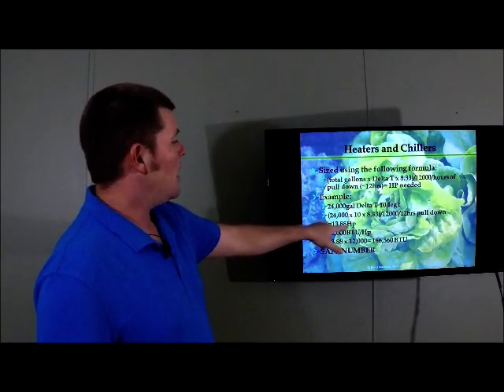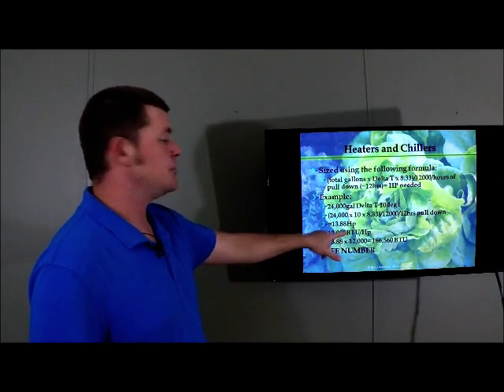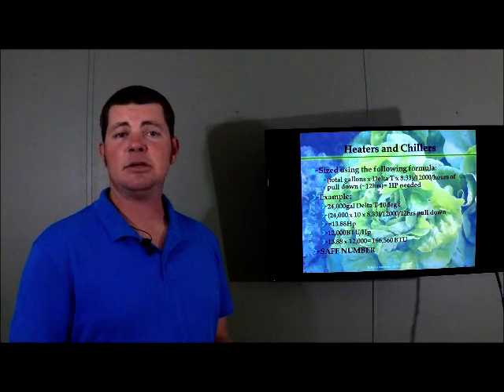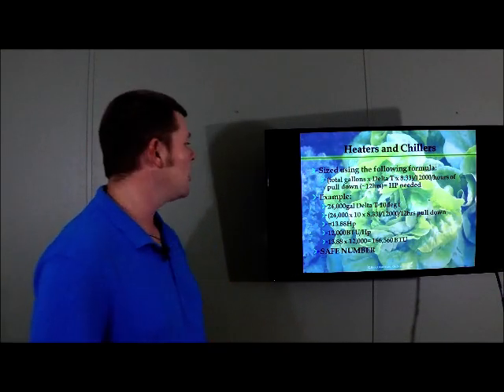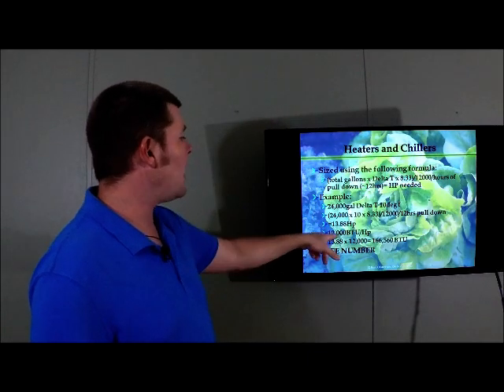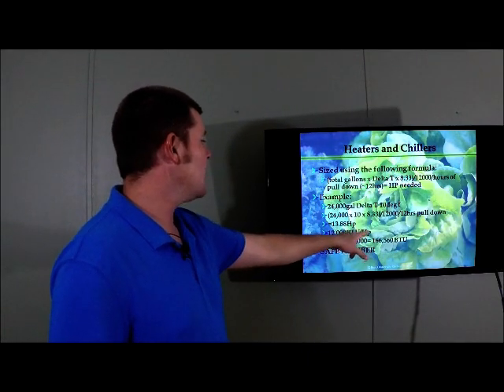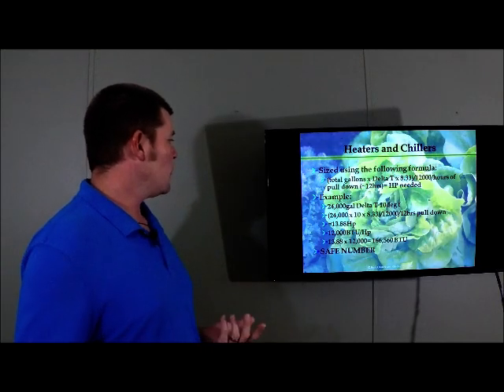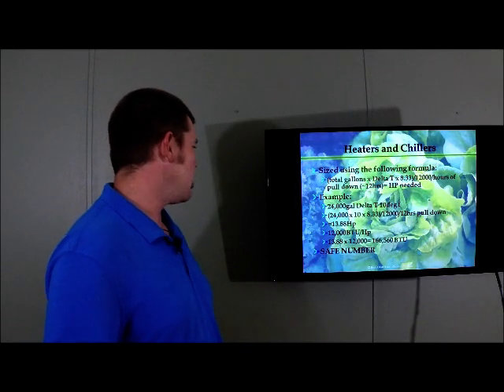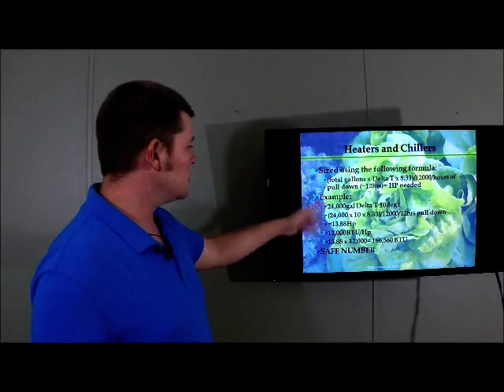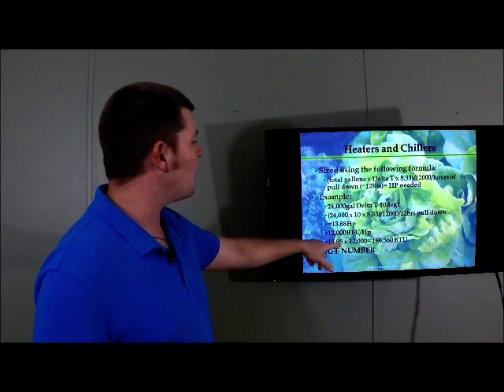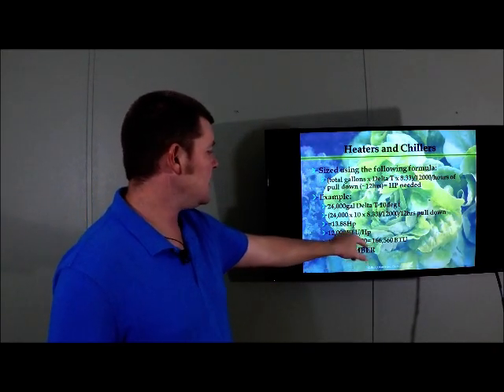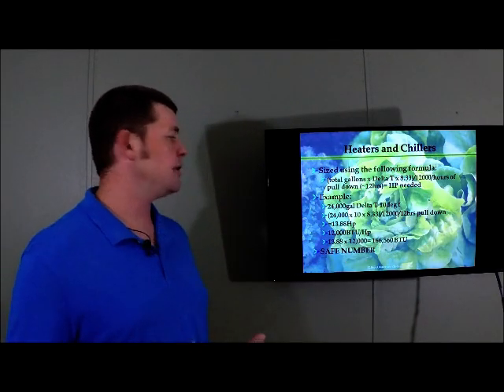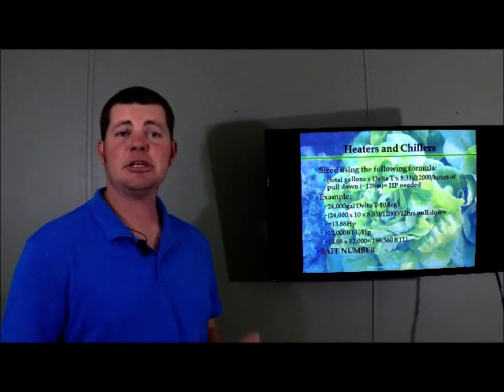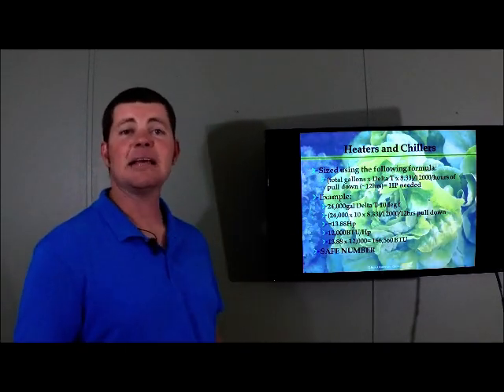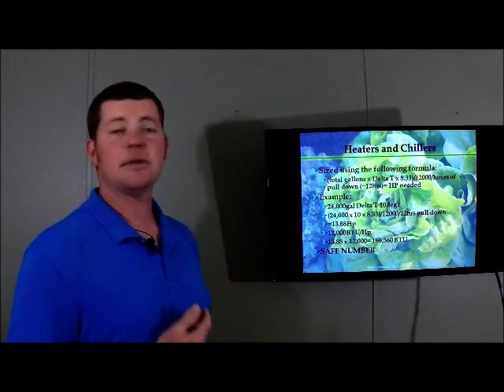13.88 horsepower can be converted into BTUs, because a lot of the units you buy are rated in BTUs. They're not going to just be rated by horsepower. So if we want to convert that to BTU, we divide 12,000 BTUs by 1 horsepower. So what's that mean? 1 horsepower is equal to 12,000 BTUs. Sorry about that. How do we do the multiplication? Easy. 13.88 horsepower times 12,000 BTUs equals 166,560 BTUs. That's the energy consumed. That's probably what you're going to use to size the actual piece of equipment. This is a safe number that's going to work.